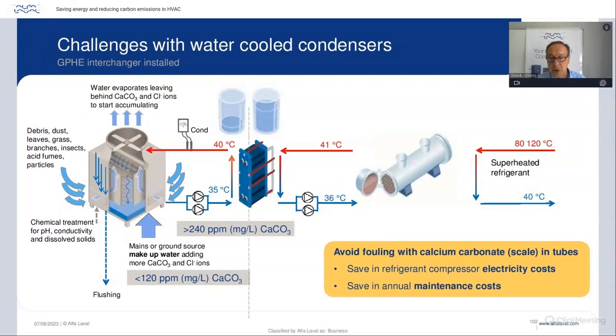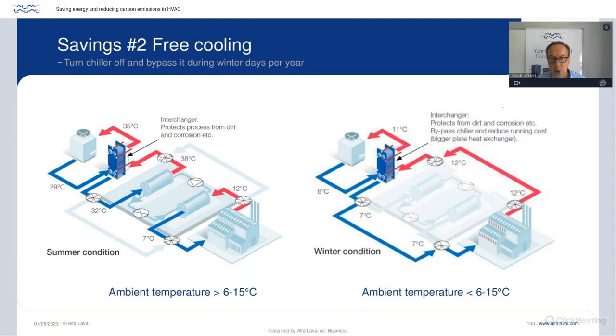Now, if we look at the second effect, one, this heat exchanger being an interchanger protects our condenser, and this is in summer condition where we have ambient temperatures of maybe 10, 15, 20, 50, whatever. So this is the summer operating condition without the free cooling.